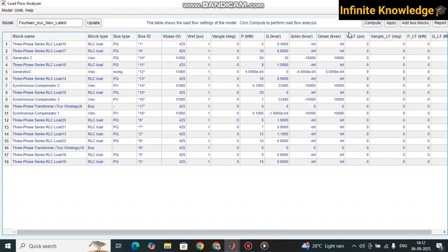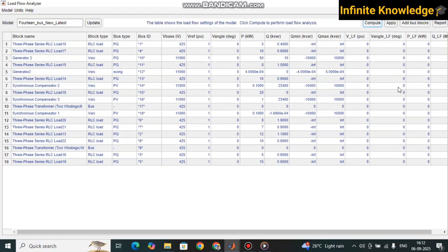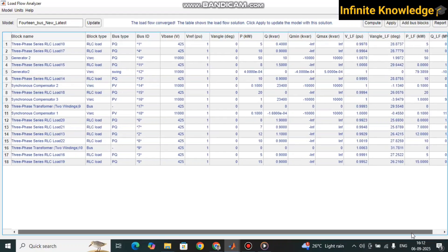You can change the units as per your requirement — I have selected kW, kVAR, and V. Before pressing Compute, note that all loads are PQ loads, one generator is a PQ generator, another is the swing generator, and the remaining synchronous compensators are PV type. Press Compute and you will see the reactive power, voltage, and voltage angle update from zero.